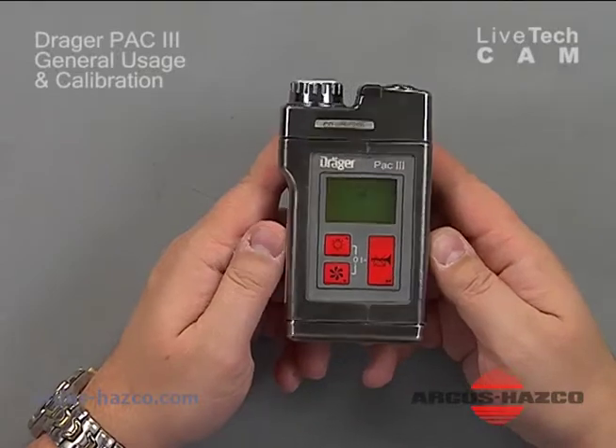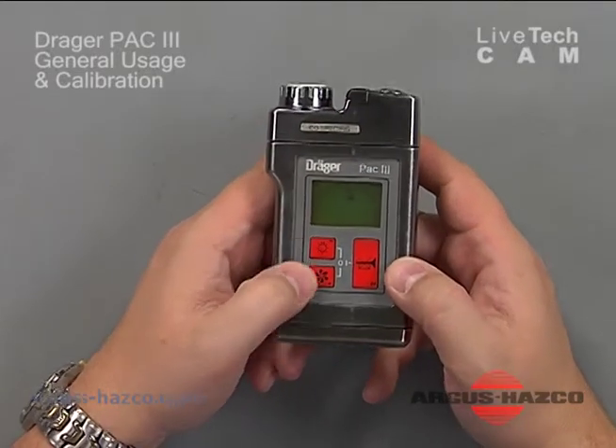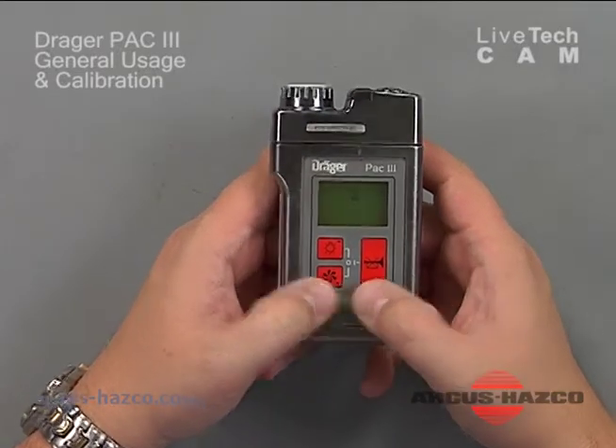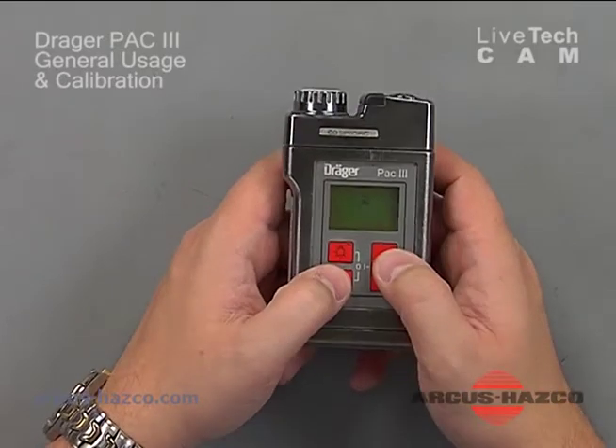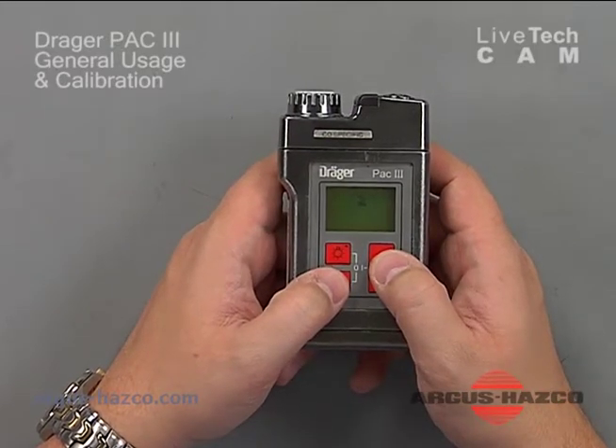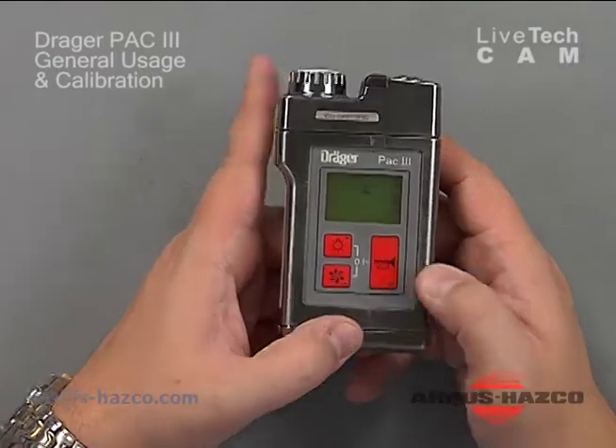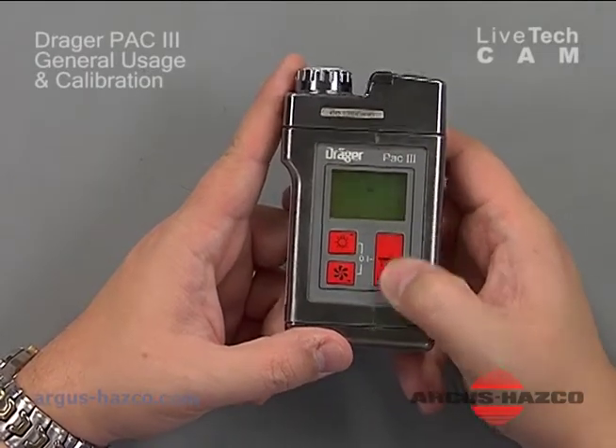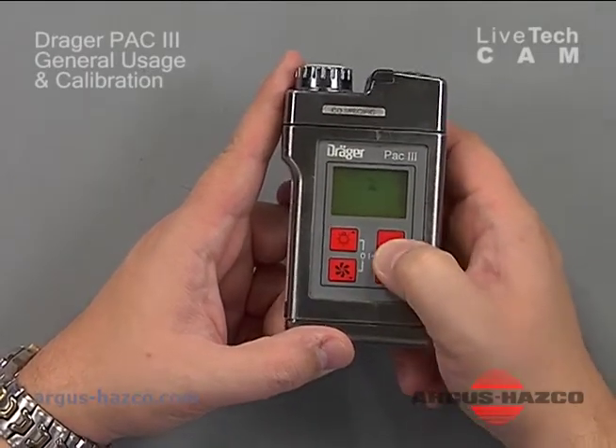So at this point, what I'm going to do is take the Draeger PAC III and turn the instrument on. You'll see there's 3 buttons on the display, and any configuration of holding these buttons will get you into different menus, which you can follow through into your user manual if you need to. At this point, to turn it on, you press and hold the big button off to the side. It has a little horn.